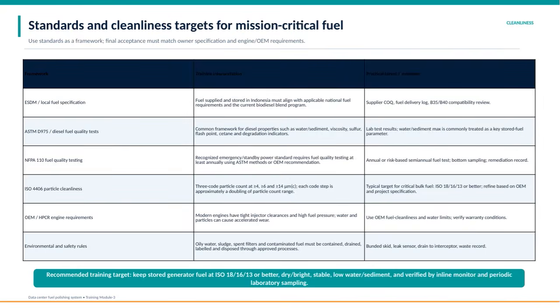When managing mission-critical fuel, it's essential to have clear standards and cleanliness targets. These standards serve as a framework, but the final acceptance must always align with the owner's specifications and the engine or OEM requirements. Cleanliness is a key focus because impurities or contaminants can lead to equipment failure or decreased reliability. Let's look at some critical frameworks and how they guide fuel quality and cleanliness. First, the ESDM or local fuel specifications ensure that fuel supplied and stored within Indonesia complies with national requirements and the current biodiesel blend program. Evidence like supplier certificates of quality, delivery logs, and compatibility reviews for blends such as B35 or B40 confirm adherence.